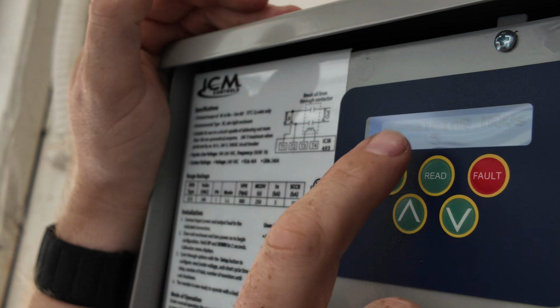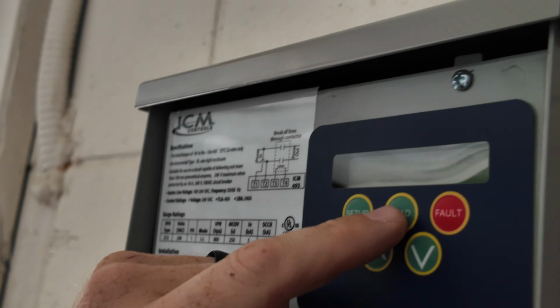This is actually reading 254 volts. I don't know if you guys were able to see that. So that's letting me know they've got a serious issue with their incoming power. So the ICM 493 is doing what it's supposed to do, and it's protecting that inverter. Now this system did have a failure with a pressure transducer on the high side, but that's because the parameters in this are set higher in order to compensate for the high voltage coming in, and that's why we have it set at a lower percentage. I would like to go lower, but then that system would be shutting on and off all the time. So I'm gonna wrap this call up, speak with the homeowner, and let them know what's going on.